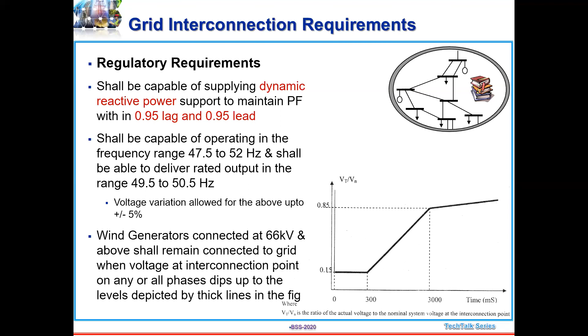There are several international regulations also: IEC 61727 for Europe, IEEE 1547 for the USA, and VDE 0126 for Germany. Actually, they are very stringent. When the utility voltage is outside certain limits, plus or minus 15%, the inverter should cease to energize within 0.8 seconds to 2 seconds, depending on the standard. More severe deviations lead to shorter intervention times. This is basically for anti-islanding protection. Again, there is a constraint on the frequency domain, and they have specified harmonics, reactive power, DC current injection, earth current, anti-islanding, etc.